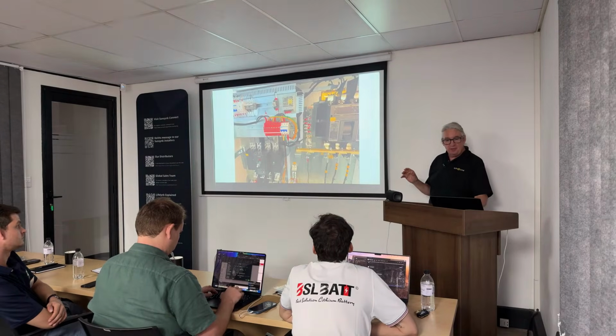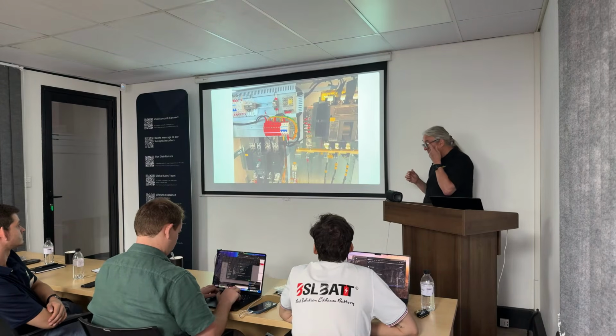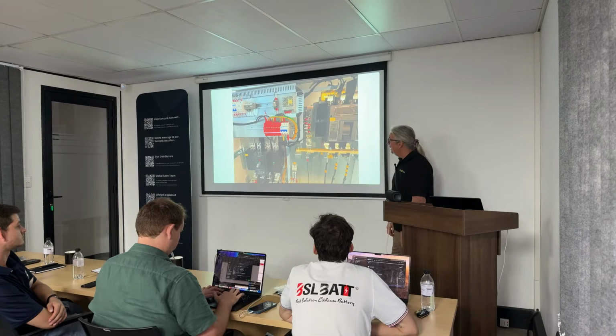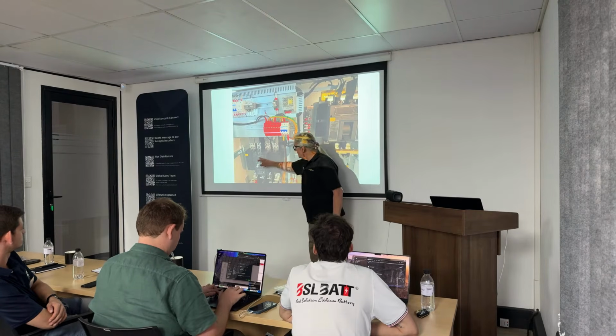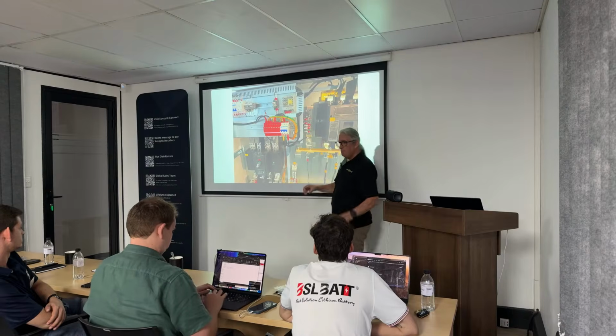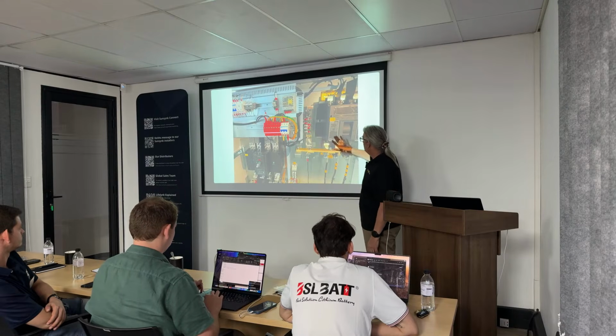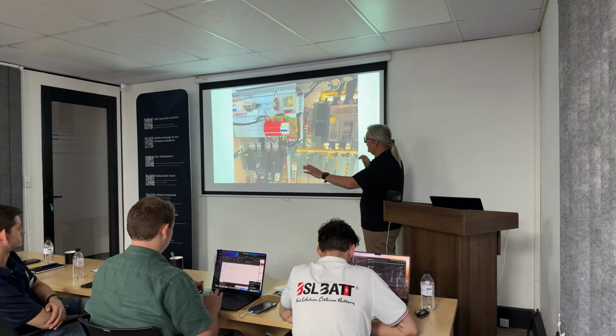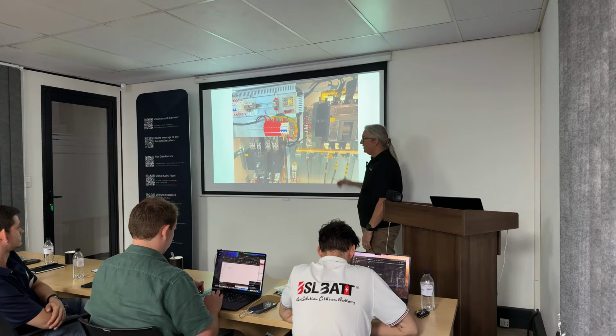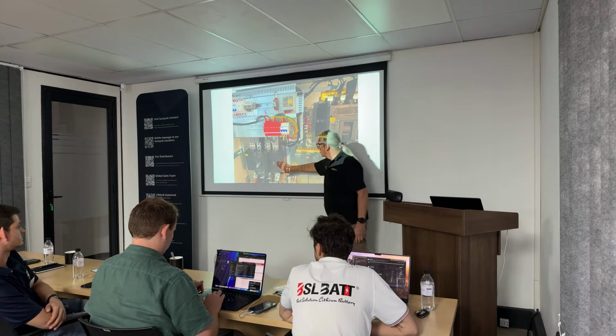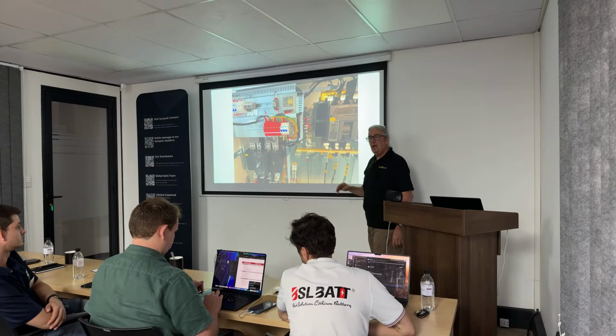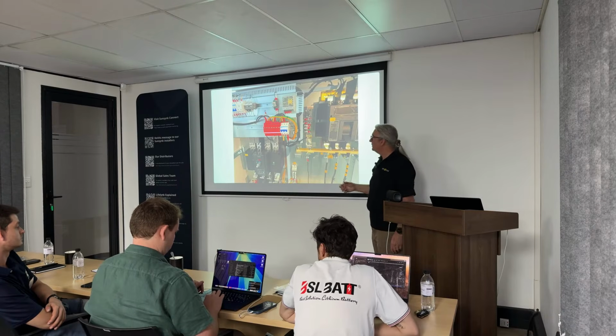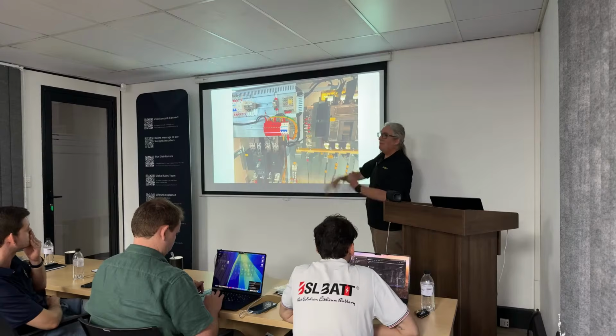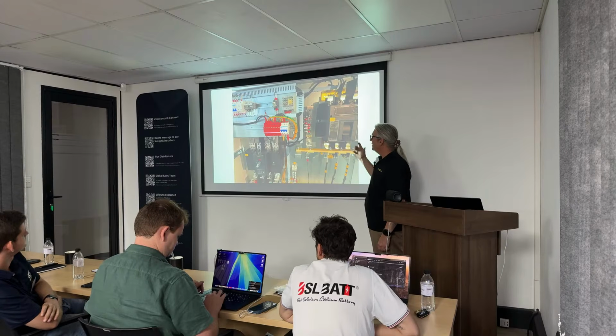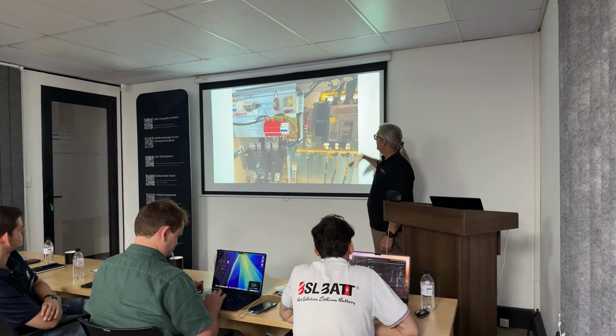Let me quickly go through this. Here is the PCS. This is the breaker, your DC breaker - each unit has a big DC breaker in it. This is your AC connections. So in the PCS cabinets you've got DC and AC. On the MPPTs you'll just have your DC breakers, and also your MPPT breakers. But in the all-in-one, everything is in there, so it's a little bit different. This is the internal.